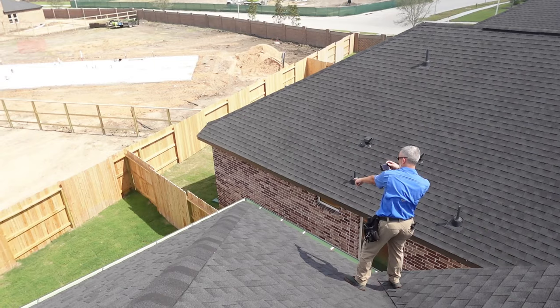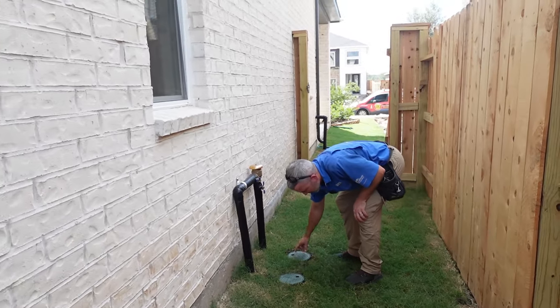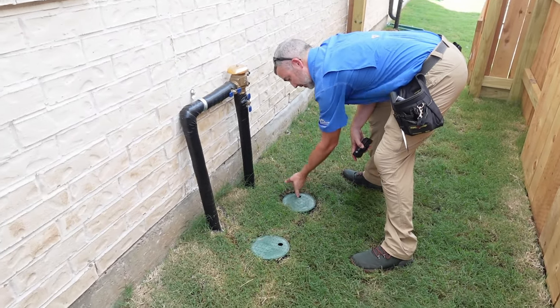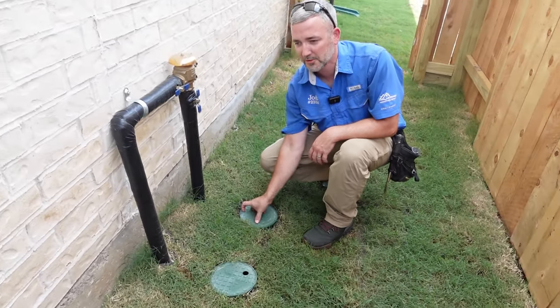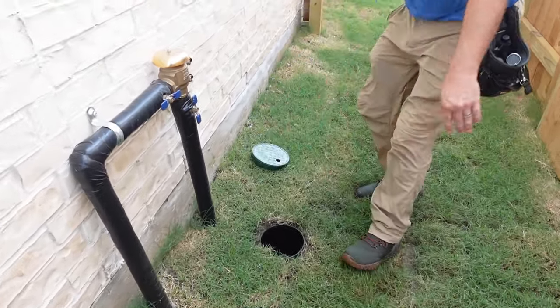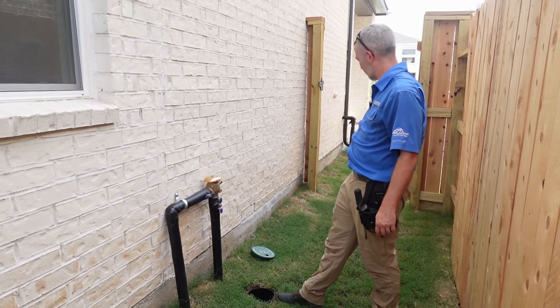There's a little bit of standing water in the gutter over here. Over here we have what should be a shutoff valve for the sprinkler backflow preventer. They have to have a shutoff valve between the water meter and the backflow preventer. It didn't have to be right here — it just has to be between the backflow and wherever the meter box is by the street.